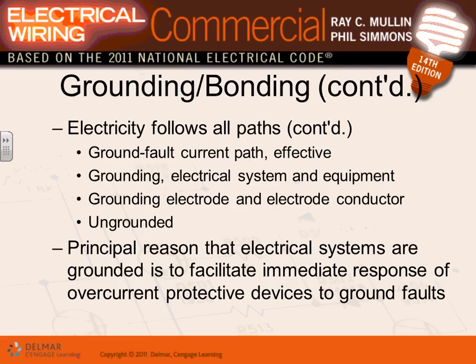Why do we ground them? Because if accidentally the frame of that fixture becomes energized, guess what's going to happen? We have a circuit breaker here that is going to see a ground fault, and immediately it will trip, indicating that, hey, do not go touch the object. It's a trap. So don't go there. So that's the main reason why we're using the ground.